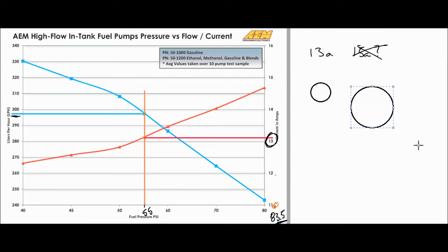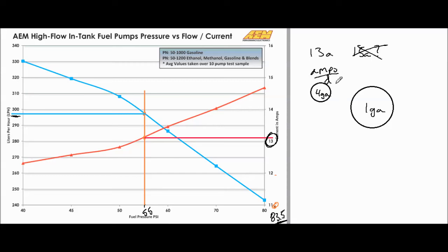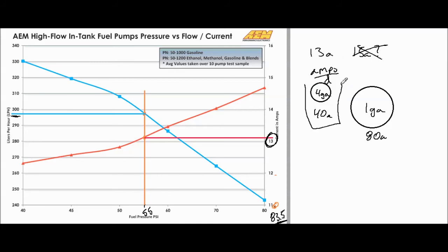The reason is wire gauge and distance. Whatever your wire run distance is will dictate the gauge of wire you can use. For example, a 4-gauge wire might handle 40 amps over a given distance, while a 1-gauge wire might handle 90 amps. With a 13 amp draw, you can safely use the appropriate gauge for that distance, and you don't need the heavier gauge.